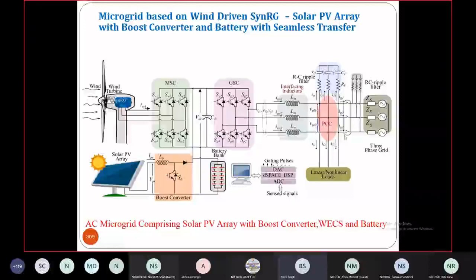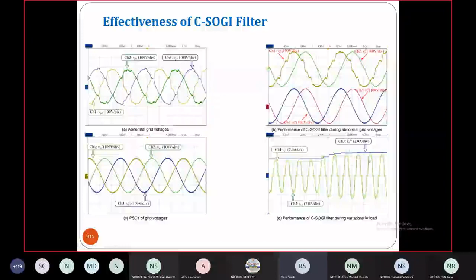So it works well with the proper control on the grid side current, and you can say the grid current is sinusoidal. The grid current THD is only 2.4%, whereas the load THD is 24.7% or so. And when the grid voltage is also distorted, we still have the grid current typically sinusoidal without much problem. So it works very well under those conditions also.